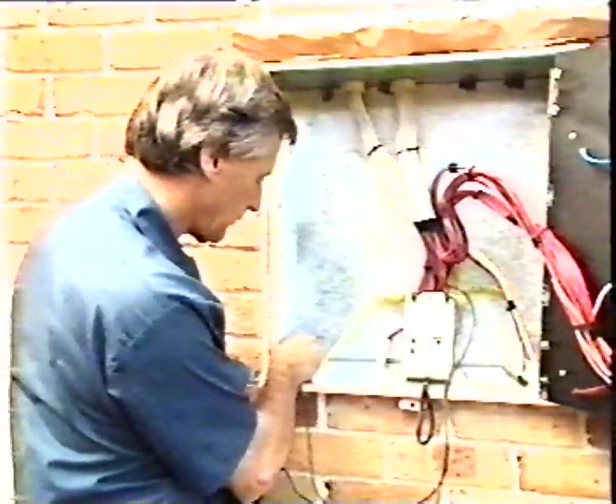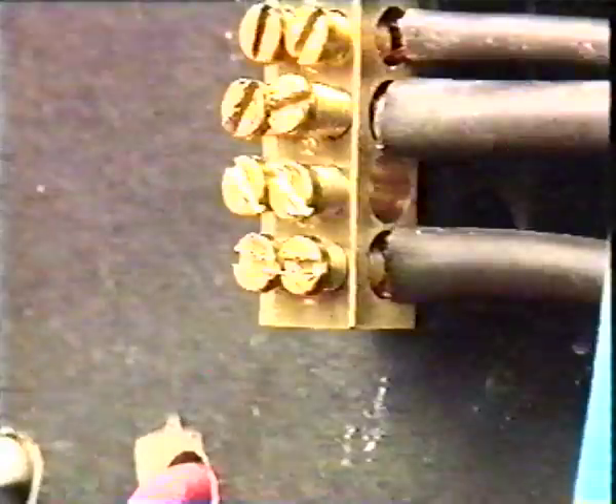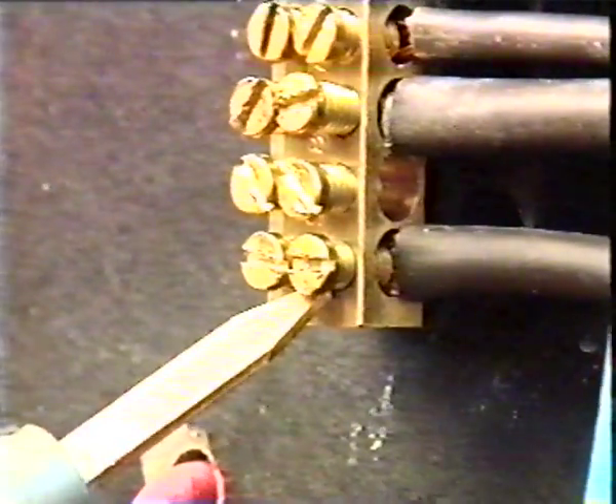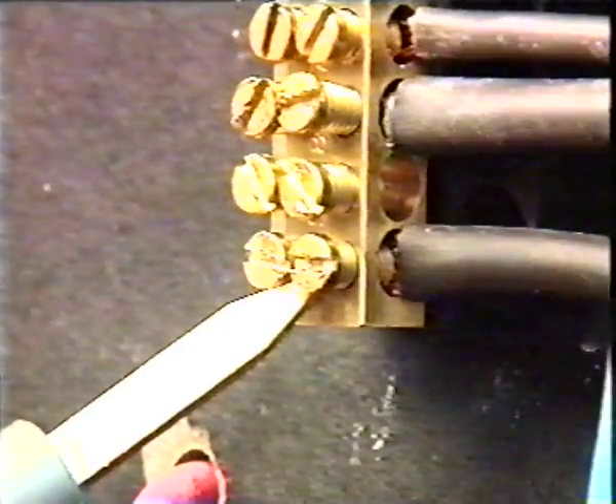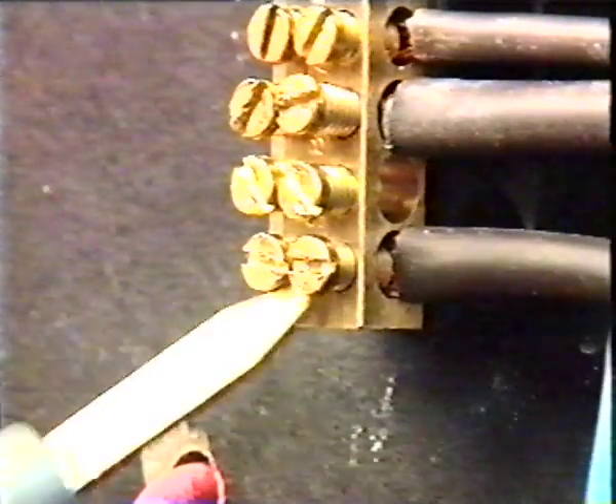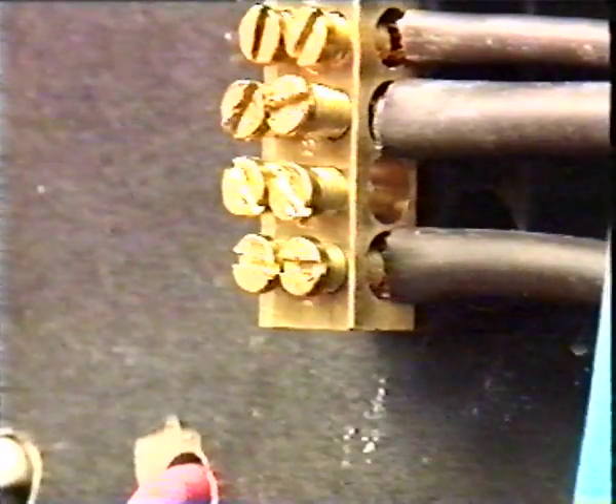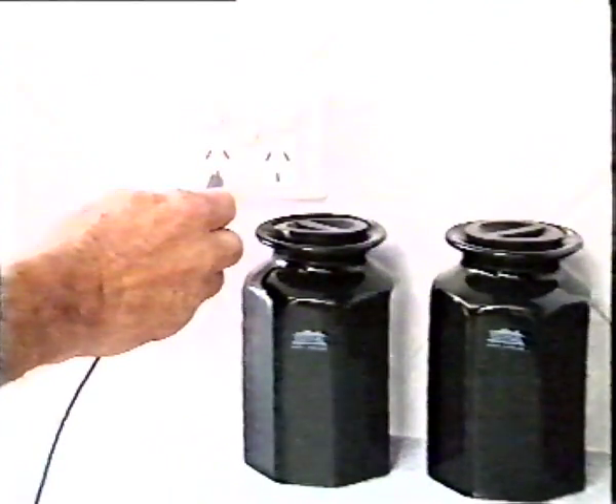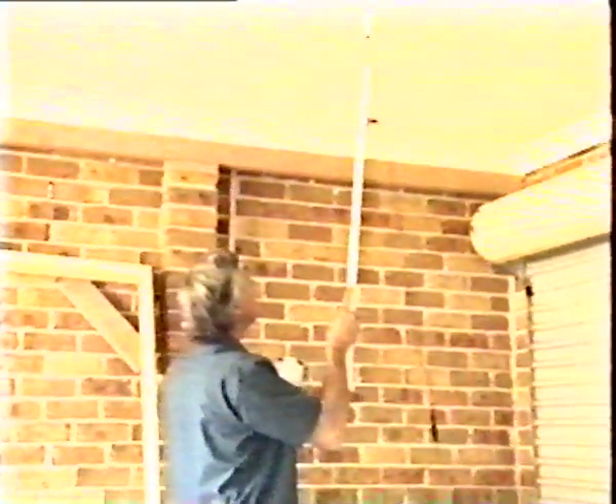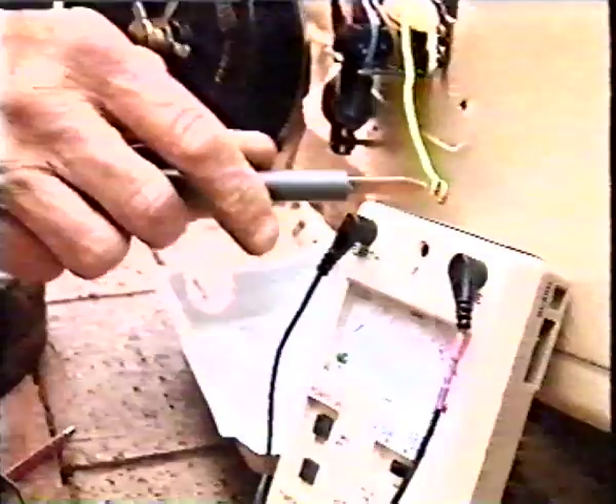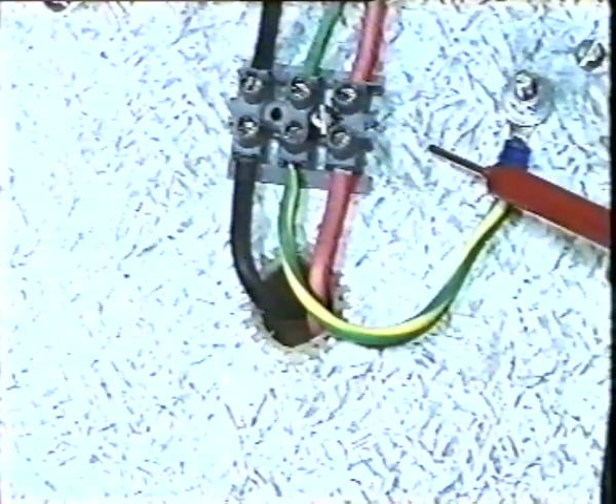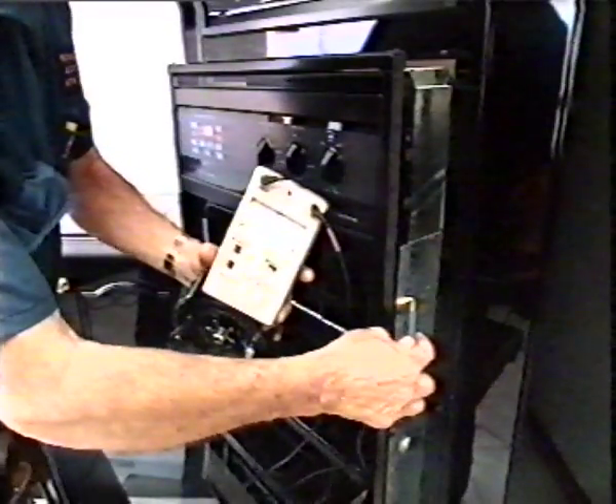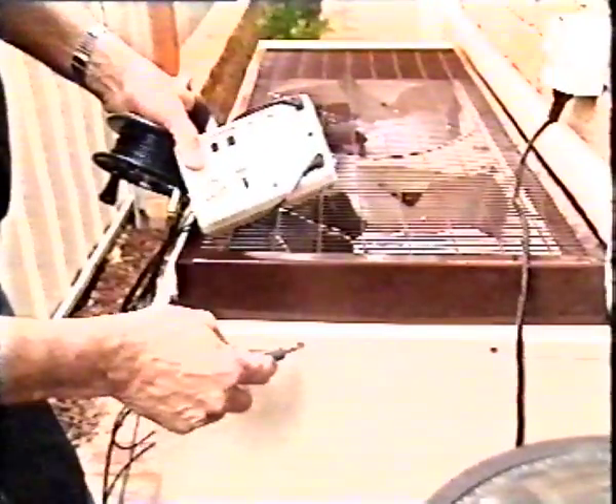for aerial conductors. In the cases of metal switchboard surrounds and metal supports for aerial conductors, both of these may be earthed by connection to the consumer's mains neutral conductor, and if so, the continuity resistance test should be made between them and the neutral conductor at the MEN connection. The earthing contact at each socket outlet, the earthing conductor or terminal at each lighting point, the earthing conductor at the water heater. Exposed metal is defined in AS3000 of any fixed electrical equipment, such as a range, oven, hot plates, luminaires, air conditioners and dishwashers.